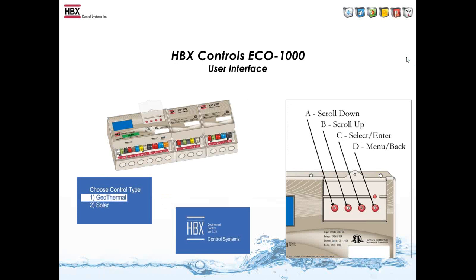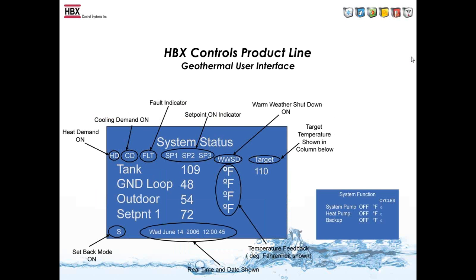When you power up the control to start, it will ask whether you want to be in geothermal or solar mode as it is a dual control. It has the same buttons as the CPU 1000 and the Snow 1000, and you can navigate your way through the control basically the same way as those two. One thing to keep in mind is that you can do a heating tank or a cooling tank, or both a heating and cooling tank in one. So it doesn't matter if you're using a dual tank or a single tank situation.